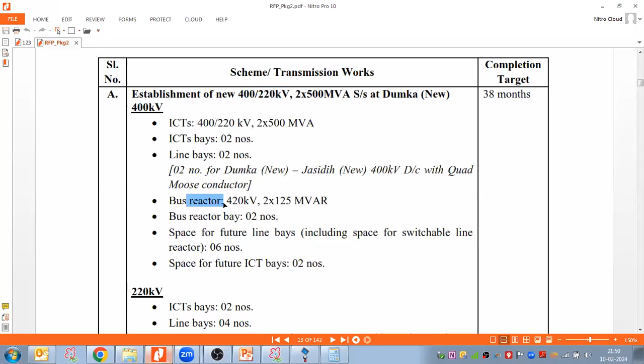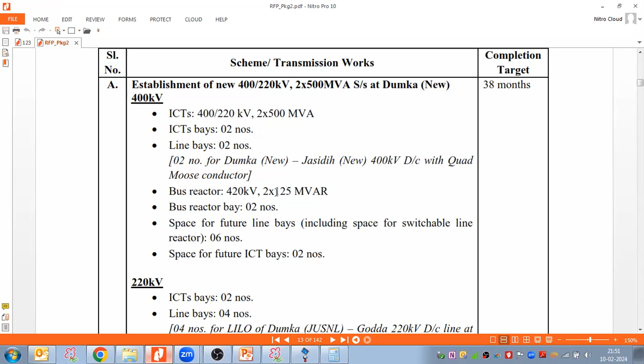So let us understand about the reactor. The reactor bay means the reactor is connecting to your bus bar, so that connecting bay is called the reactor bay. This is just a simple thing. So here I'm using 2 reactors of 125 MVAR. Reactor rating comes in VAR. The transformer rating comes in MVA. So please note down the difference in that. Here, if you see, ICT 400 by 220 kV, 500 MVA, and here MVAR. So 2 reactors, and due to that, here 2 reactor bays. So let us come to the reactor now.